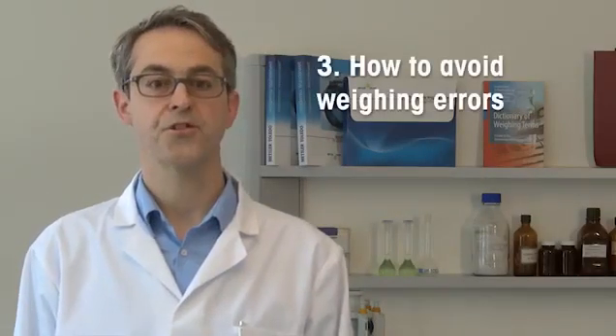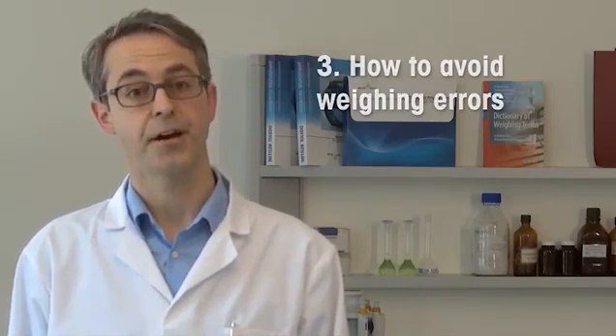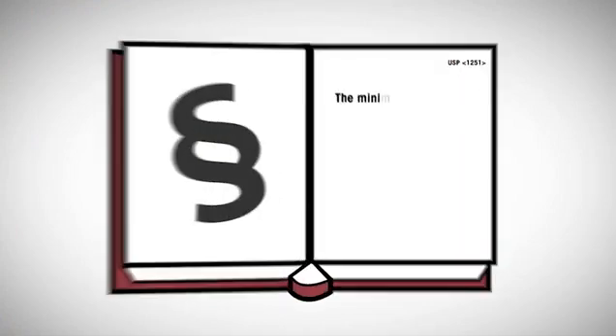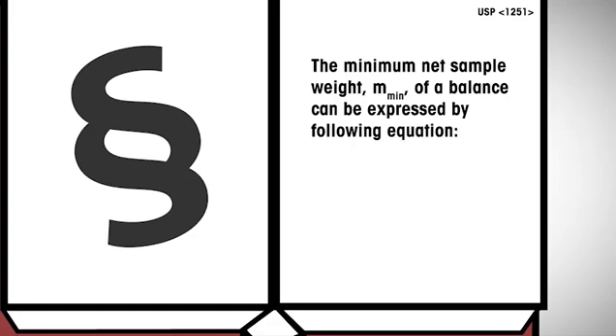The last thing you should know about the new USP weighing chapters is how to avoid weighing errors. The minimum net sample weight, Mmin, of a balance can be expressed by following equation. We've already seen the Chapter 41 criteria for repeatability. Solving this equation for the mass yields that the minimum weight must be equal or larger than 2000 times s.